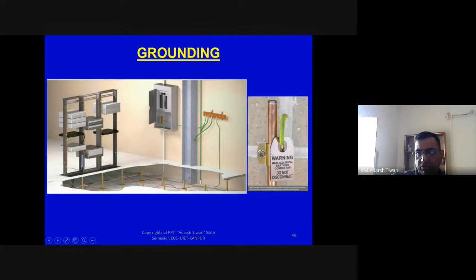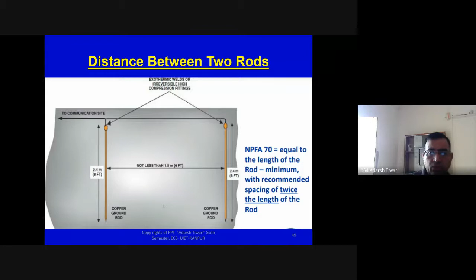Whenever we are doing any grounding as per the NFPA 70 standards, we have to see the grounding rods' minimum depth, which is 8 feet, and between the rods where we are doing the grounding, the minimum is 1.8 meters. Whenever we are installing any grounding system, we have to consider what conductor, AWG, American wire gauge, what the dimension is, and how much of it is to be inside the ground.